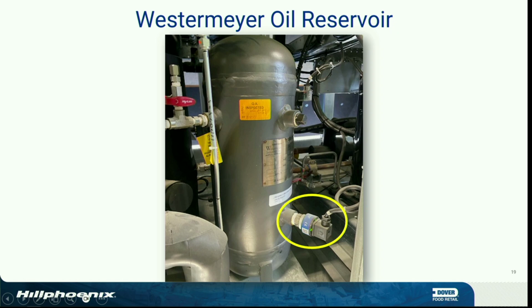If you have a problem with these sensors, pull them apart. Those plugs, you take that screw out right there, pull it apart. You can push that wire down and pull the plug section of that out and make sure your wires are good. All right? Even if it's been working for 6, 7 years, all of a sudden it quits working, check your power head too. You got 3 numbers on there, 1, 2, and 3. 1's your 24 volt DC, 2 is your common for power, and 3 is your switch light.